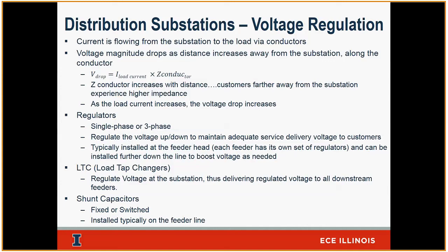the voltage here is a function of two elements. So V is equal to the load current, so whatever the loads are drawing, multiplied by the impedance of the line. A voltage drop is calculated by doing that times, again, the impedance seen away from the substation. So if you're close to the substation, your impedance is low, right? So the voltage drop is going to be low. That's just a direct relationship. As you go farther and farther away from the substation, your impedance is larger, right? The amount of copper you've got, the amount of line you've got. And the farther you are from the substation, the larger the voltage drop you have in here.